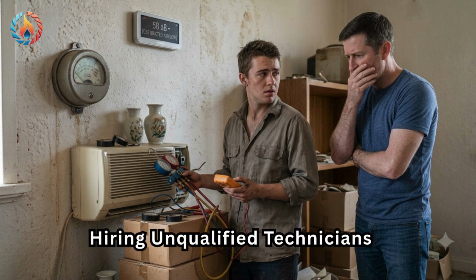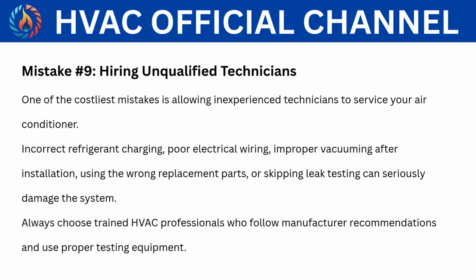Mistake number 9. Hiring unqualified technicians. One of the costliest mistakes is allowing inexperienced technicians to service your air conditioner. Incorrect refrigerant charging, poor electrical wiring, improper vacuuming after installation, using the wrong replacement parts, or skipping leak testing can seriously damage the system. Always choose trained HVAC professionals who follow manufacturer recommendations and use proper testing equipment.